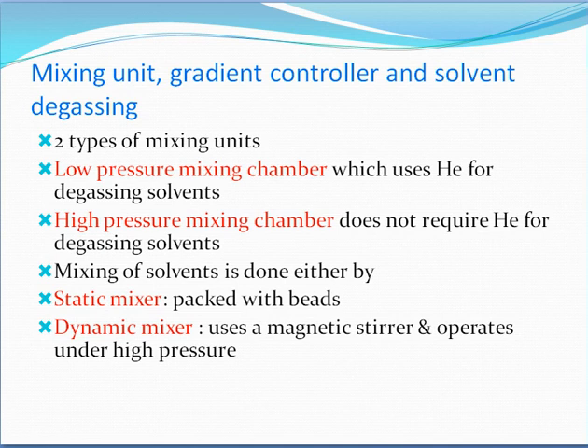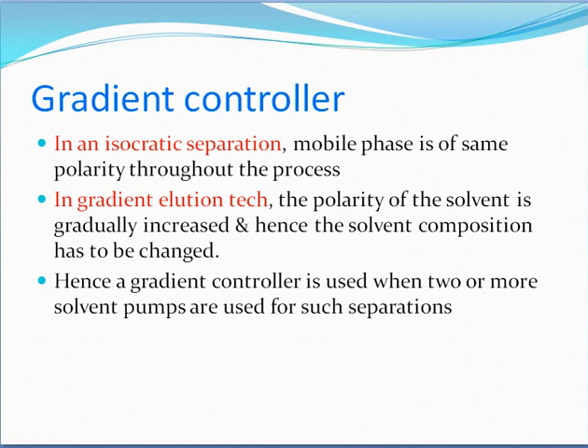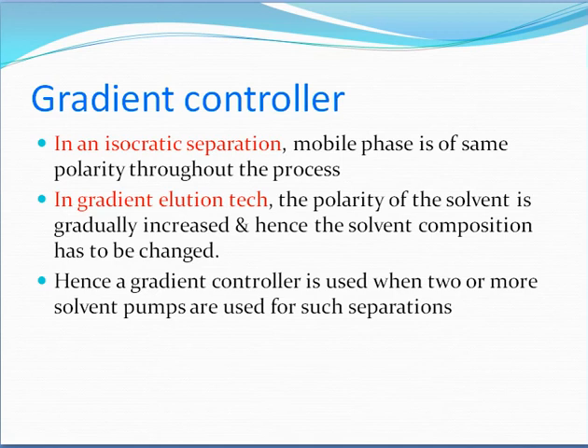The dynamic mixer uses a magnetic stirrer and operates under high pressure. The gradient controller manages solvent composition during separation. In isocratic separation, the mobile phase polarity remains constant throughout the process. In gradient elution, the polarity of the solvent is gradually increased, so the solvent composition must be changed, and a gradient controller is used when two or more solvent pumps are used.